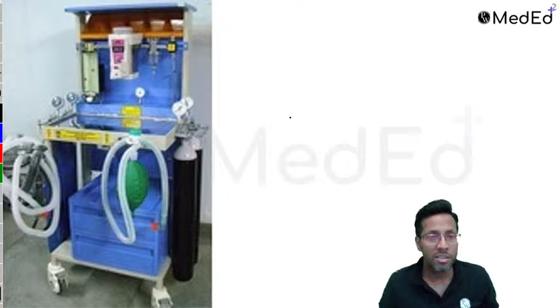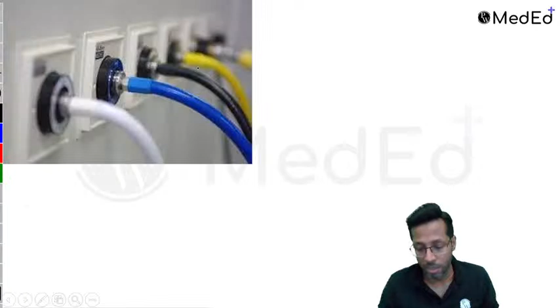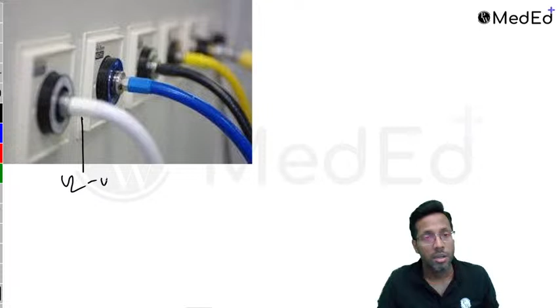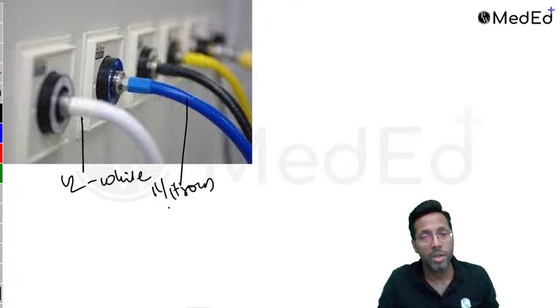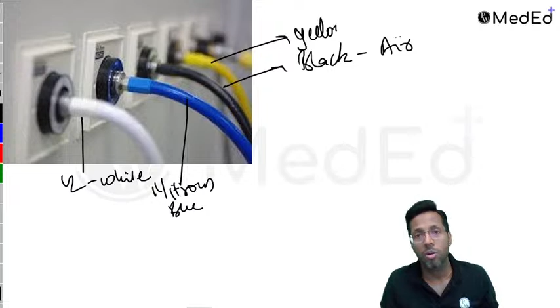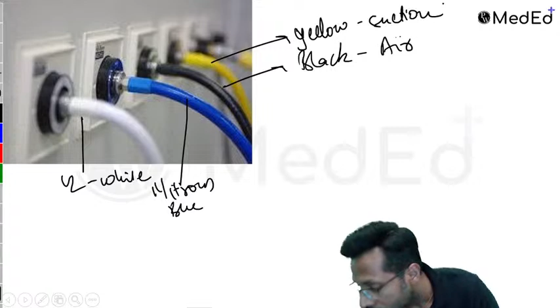On the anesthesia machine, because these cylinders are used in emergency, you've got a pipeline supply also coming, right? These pipelines also have those colors where you will find oxygen is always white in color, nitrous is always blue in color, right? This black is air, and air is provided where we use it in anesthesia, like in laparoscopy where we don't use carbon dioxide, and this is vacuum, which is yellow in color, right? The yellow color that you see is called vacuum, which is used for suctioning. These are the pipelines.